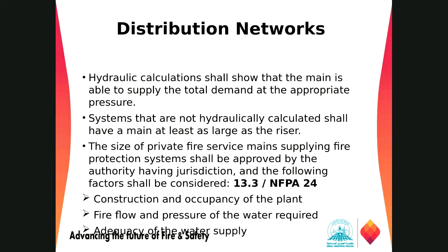We have to do the hydraulic calculation for the underground fire water networks, and we have to make sure that the pipe is sized exactly for our total demand, right? What we have calculated for our fire protection system. And those systems that are not hydraulically calculated shall have a main at least as large as the riser, right?